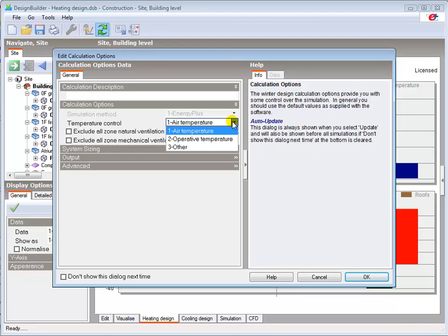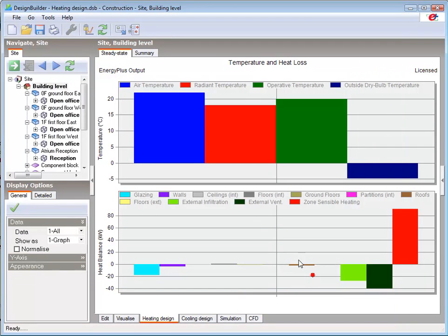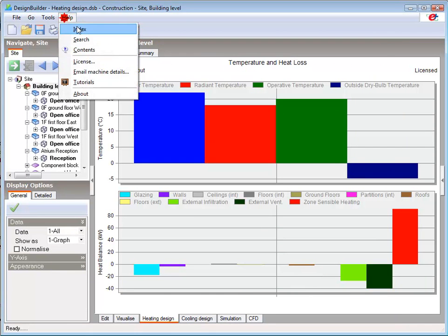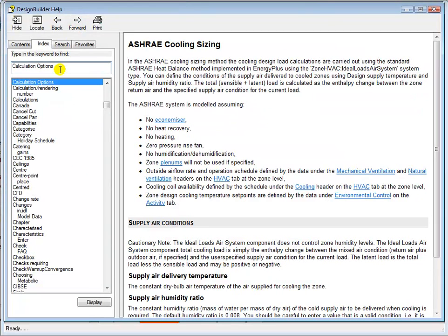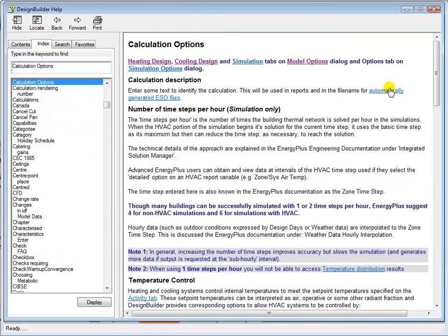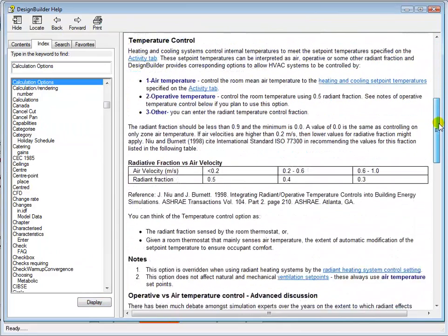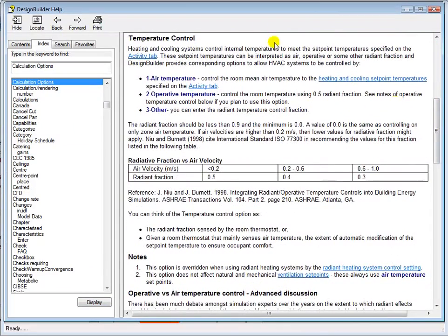For example, calculated plant sizes will normally be lower when air temperature is selected as a controlled parameter. A very useful discussion on the impact of using the different types of temperature control is included in the help file, which can be accessed by typing in the text calculation options here in the help index.